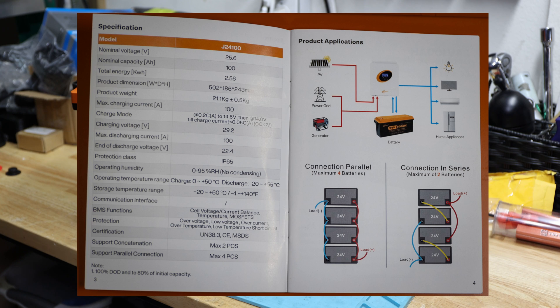The max discharge current is 100 amps, and the end-of-discharge voltage is 22.4 volts. The protection class is IP65. The BMS protections listed include over-voltage, low voltage, over-current, over-temperature, low temperature, and short circuit protection. On the second page, they show parallel and series connection options: a maximum of four batteries in parallel and only two in series if you want to reach a 48-volt configuration.